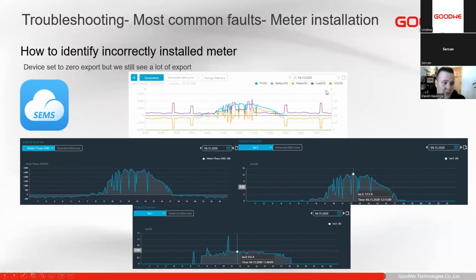So I went to SEMS portal. I saw, okay, we can see it is exporting, but it's not supposed to export. Let's see whether it is a meter installation issue or something else. So I went to meter phase 2. Well, phase 1 didn't have it. Phase 2, yeah, I could see here's the data that's probably showing the export is on meter phase 2, because phase 3 and phase 1 didn't really have any export on them. Then I go to IAC2 to view the AC output of the inverter, and I see the inverter is not producing any notable power on output number 2.